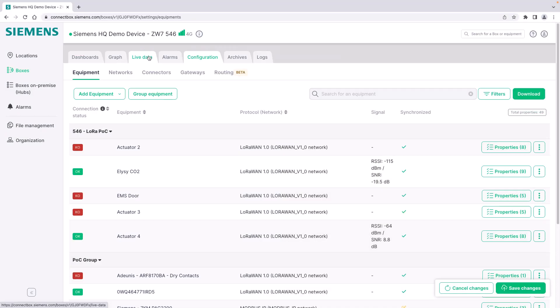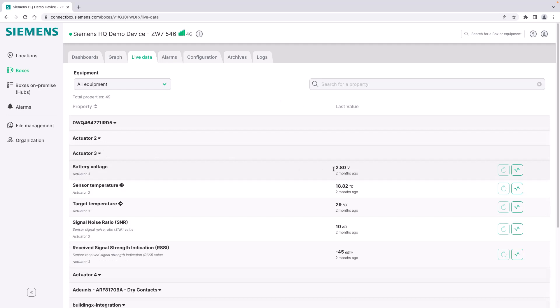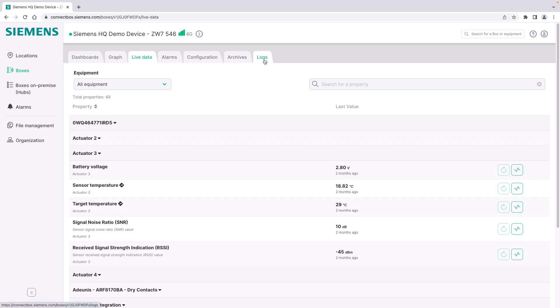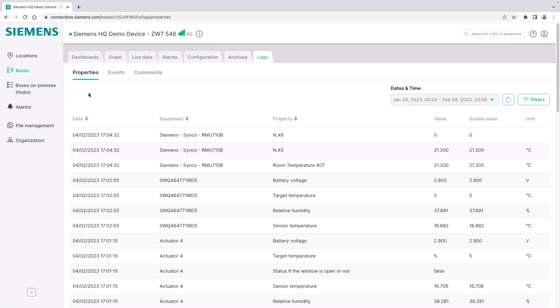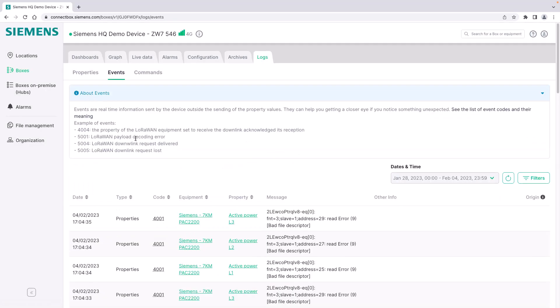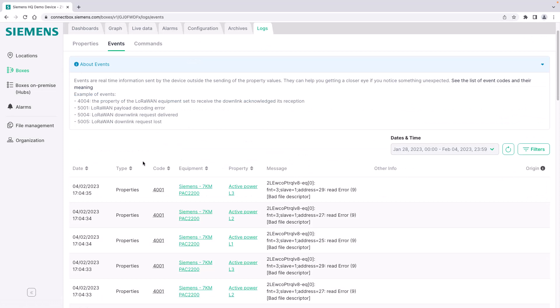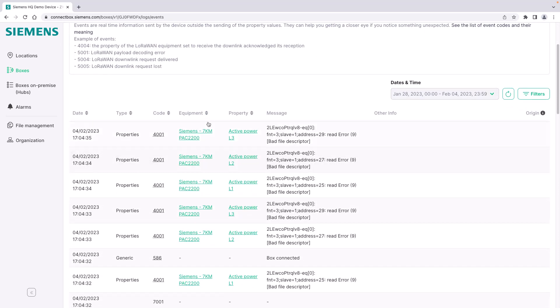One way to troubleshoot is accessing the live data of the devices. For example you can check here when was last time data transmitted - this one seems to have a problem, last data two months ago. So if you want to go deeper you can have a look at the logs and in the logs you can look into the properties that have been received here during the last week. You can have a look at specific events, that's especially helpful for traditional field bus protocols such as Modbus and LoRaWAN. You can see here different properties and log entries of the devices I have connected.